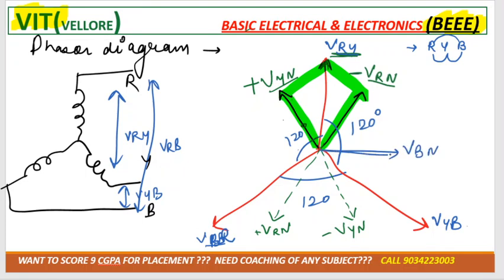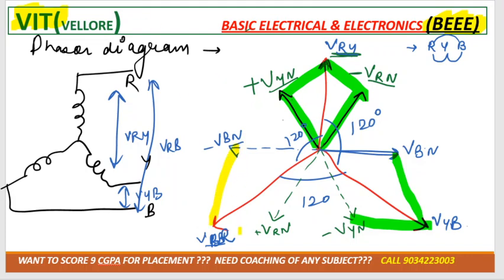Always draw the phase voltage line as a straight line because you need to extend it. If VBN is positive, extending gives minus VBN. So VYB has two components: VYN and VBN. VBR has two components: VBN and VRN. The angle between the line voltage and the phase voltage is always 30 degrees.